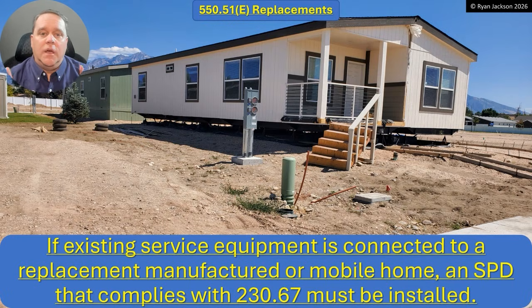All right, so here I've got this mobile home that has been there for 20 years. It decides to take off. We put a new mobile home in its place. The surge protection requirements of 230.67 now need to be followed, which means at the panel board in the manufactured home or mobile home, you're going to put in a surge protection device. All right, so there you go.